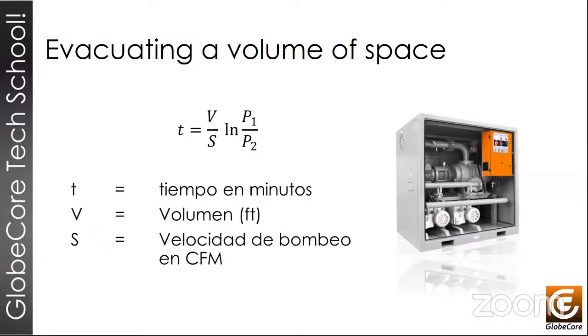This information can be found in the excellent book by Ernesto Gallo. It's called Field Service Manual for Transformers, and I can't recommend it enough. It's a great book. Here, in this formula, we can see how long it takes to reach the required vacuum depending on the volume. The volume is V, the rate of the pump is S, and then the ratio of the initial pressure and the target pressure that we need to reach. Next slide, please.